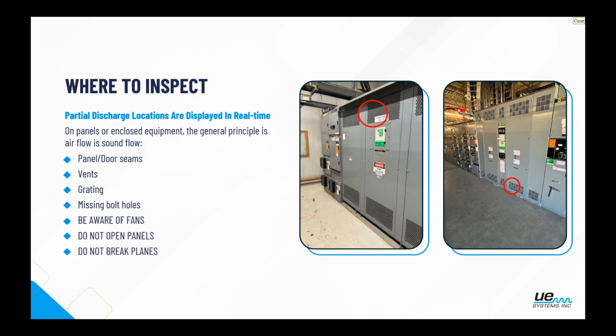And in the example on the right, we heard a moderate to fairly faint signal coming through from that bottom grate. When we inspected from the top, it was almost missed. So once again, if you have the option to inspect from the top and the bottom, do it. You might pick up something better from one than the other to make that recording easier, or you might actually miss it if you don't inspect from both points. And as you saw in that video at the beginning, the speed of inspection doesn't make it overly time consuming.